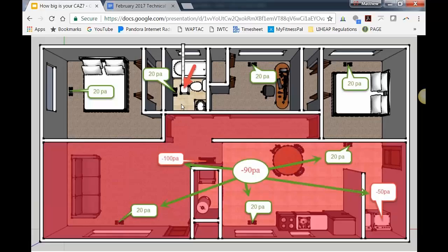Right, but what I'm saying is that if the CAZ got a test because they adjusted the fan, that shouldn't have technically happened. It should have been tested at high in the beginning, at the highest rate possible. Well, they had it set intermittently, where it was only kicking on like 30 minutes out of every hour.